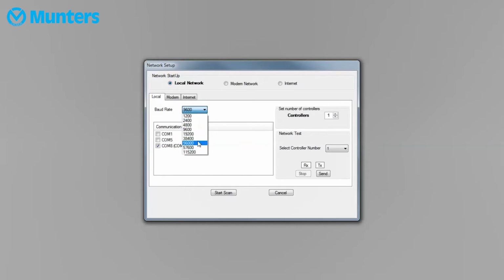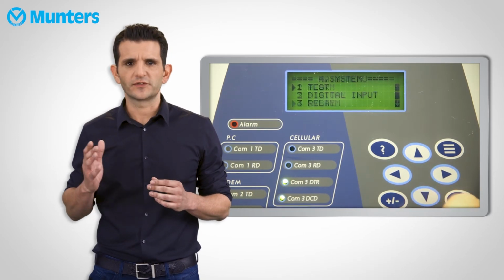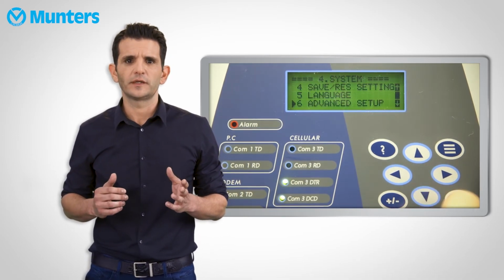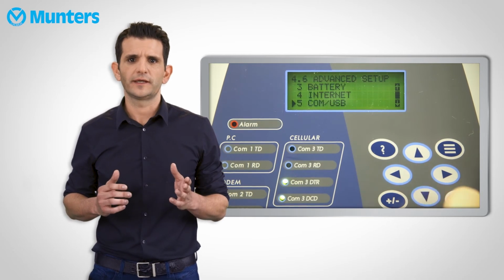One other critical parameter is the baud rate, which is the speed of communication between the communicator and the PC, and must match on both sides. In the communicator, go to System, Advanced Setup, and then COM/USB, and define the right speed. On the PC side, open ROADMnet, and then Setup, and check the baud rate. We usually work at 9,600 bits per second, except for SuperGuard that runs with 4,800 bits per second.